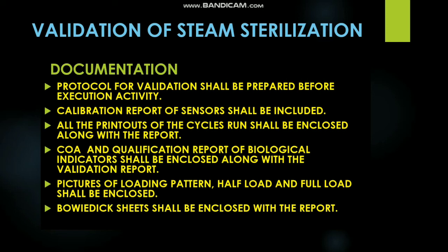Similarly, the full load should be specified, and the loading pattern of the articles in full load should be specified. They should be part of your validation protocol. The validation protocol shall be prepared before execution of the qualification activity. Then the calibration report of the sensor shall be included in this report. All the printouts of the cycles run shall be enclosed along with the report. The COA and qualification report of the biological indicator shall be enclosed along with the validation report.